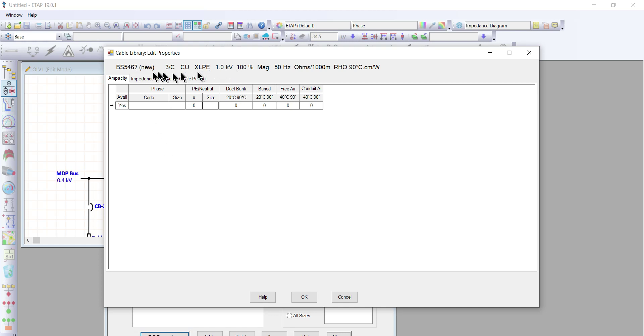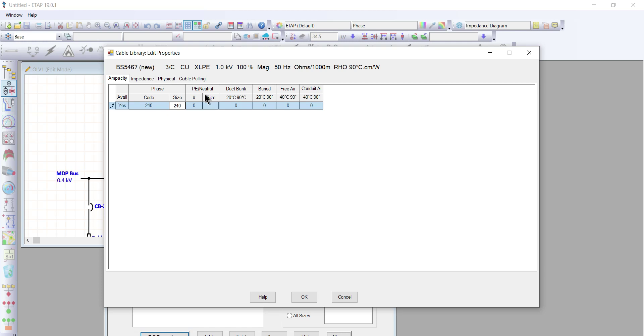We have four sections: ampacity, impedance, physical characteristics of the cable, and cable pulling parameters. For the ampacity, since we're proposing a 240 mm² cable, let's type 240 here for the cross-section and 240 for the size as well. Since we don't have a straight core, PE and neutral are not included, so we'll leave those empty.